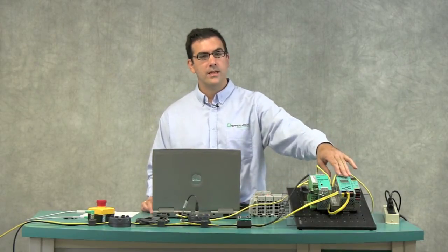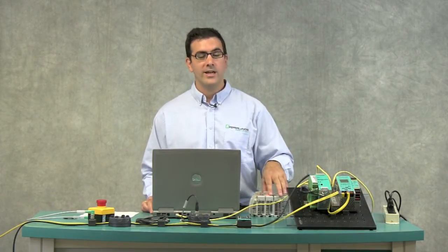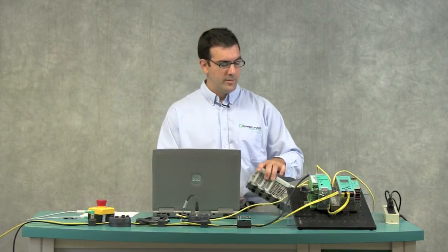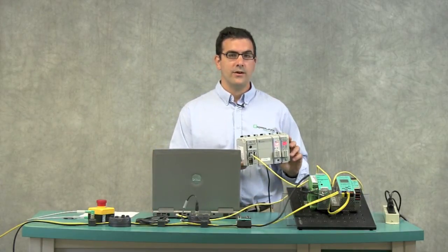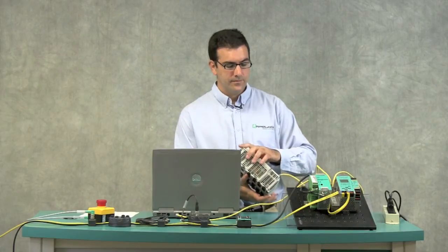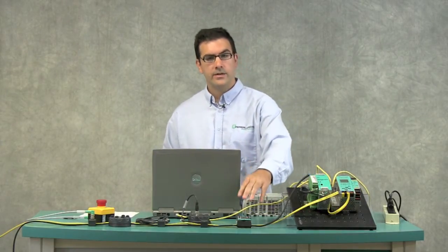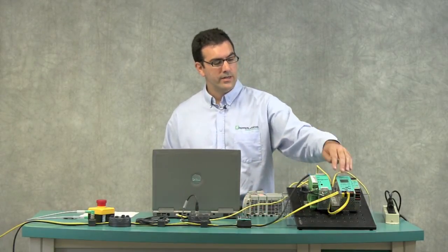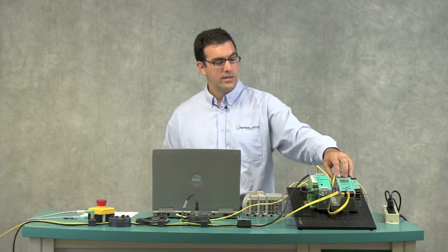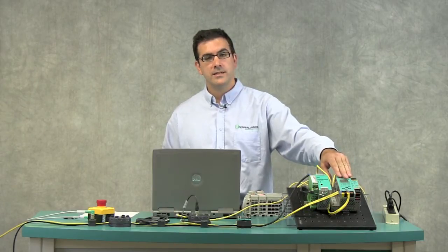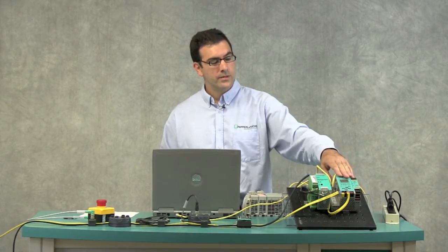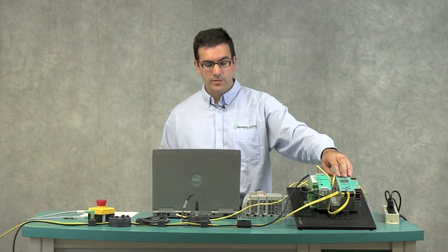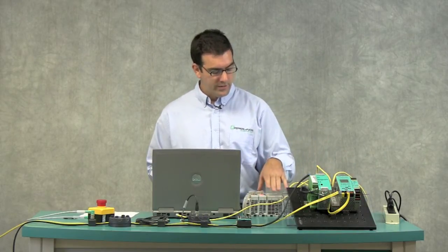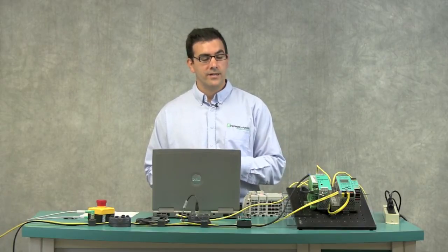And today I'm going to be talking about programming the AS Interface Ethernet IP Gateway with an Allen Bradley PLC. I'm going to be using the Compact Logix L32 PLC. My AS Interface network has been completely configured and I've done a store and run on the gateway. My IP address, subnet mask, and gateway have all been configured inside the unit using the keypad and display. So now all I have to do is open my RS Logix 5000 software and configure it.